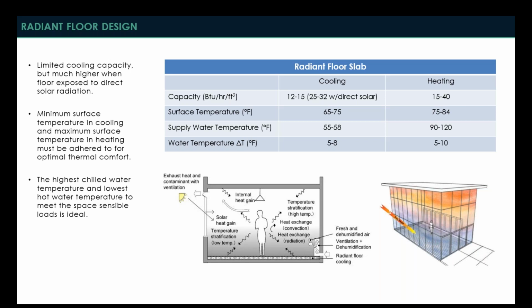On the heating side, there's a bigger, I would say, band of heating capacity possible with the floor. Anywhere between 15 and 40 BTUs per hour per square foot can be achievable. And a lot of that is going to depend on the surface temperature and what supply water temperature you're using. And that's a good segue to talking about surface temperature. So because people are going to be in direct contact with the radiant system when you're using a floor slab, the surface temperature and maintaining the appropriate surface temperature is very, very critical.